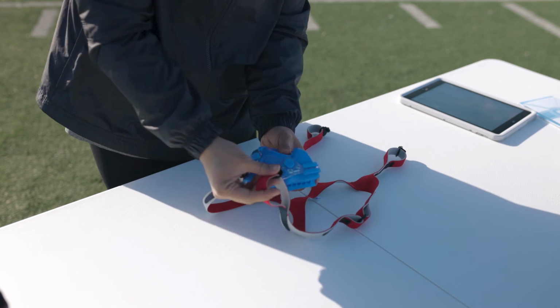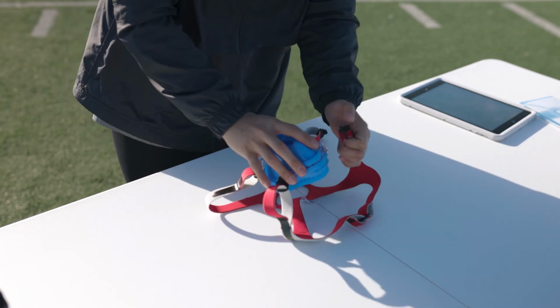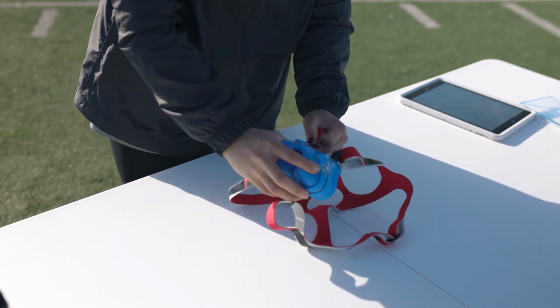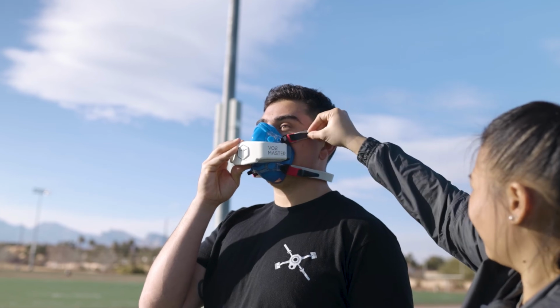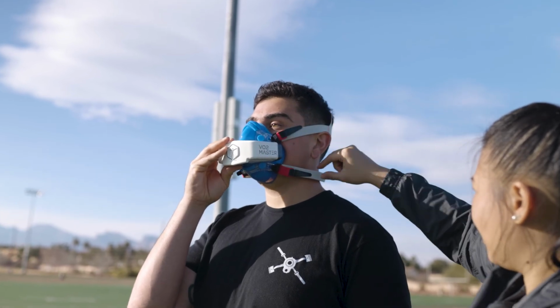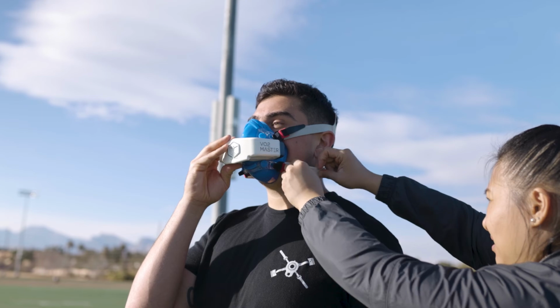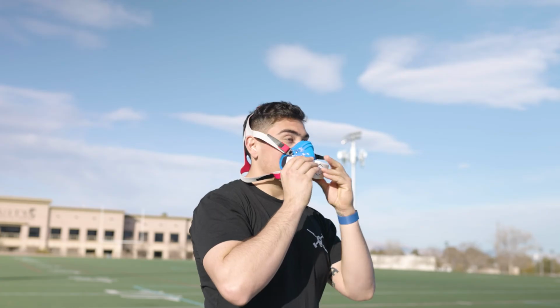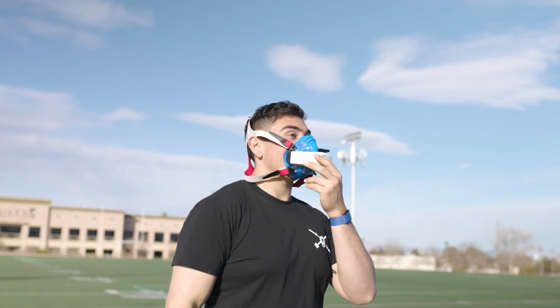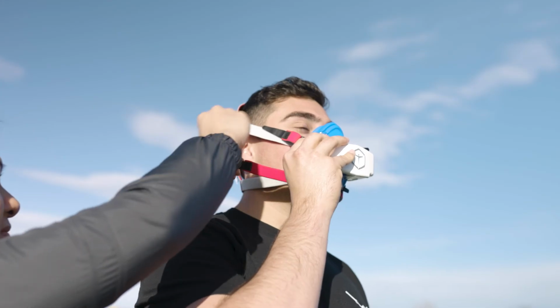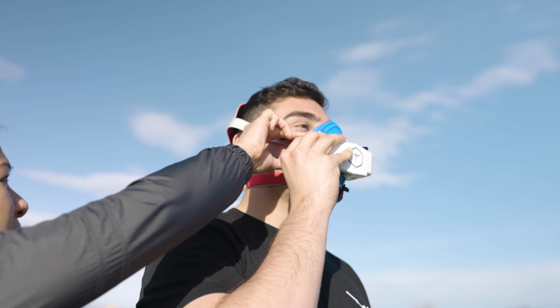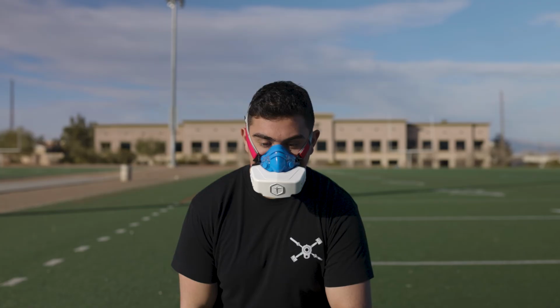Connect the headgear to the mask by sliding the black fasteners into the clear receivers on the mask. For an easier fitting, loosen the Velcro tabs and place them off-center to easily access later when tightening the fit. Have your participant apply pressure to the mask to reduce the likelihood of air leakage. Finally, adjust the Velcro straps accordingly to ensure a tight fit. Now you can run a metabolic test.